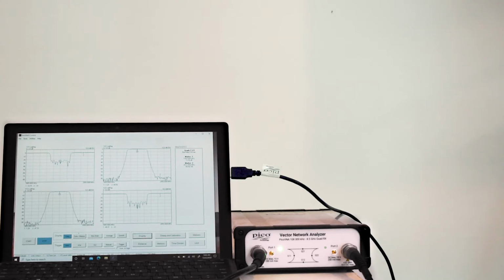Now we move on to the next phase in the field calibration procedure, which is setting up calibration parameters. In the main window, click Calibration to open the calibration window, in which the following steps are to be performed. Set the sweep parameters. This is similar to setting up a spectrum analyzer. After setting bandwidth, apply values. Select the measurement required. Perform the calibration steps. Finally, click Apply Calibration. The bandwidth setting used during calibration largely determines the available dynamic range during the measurement.